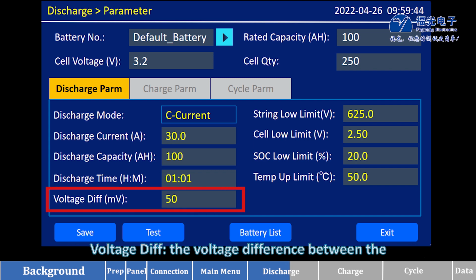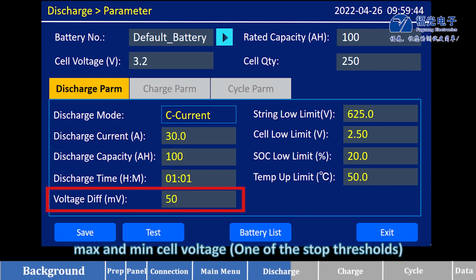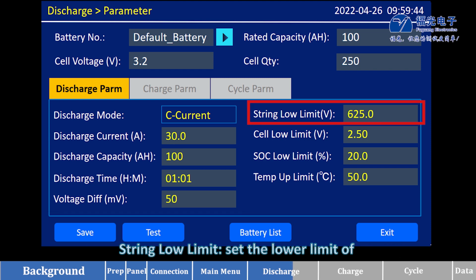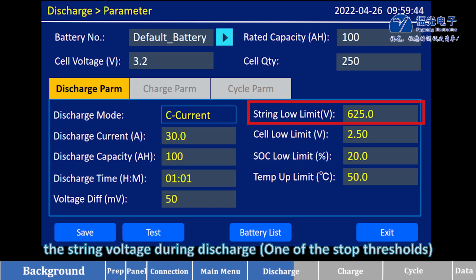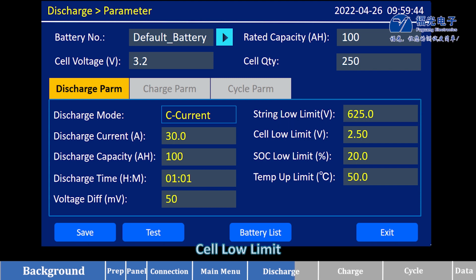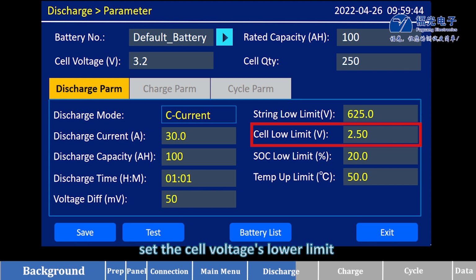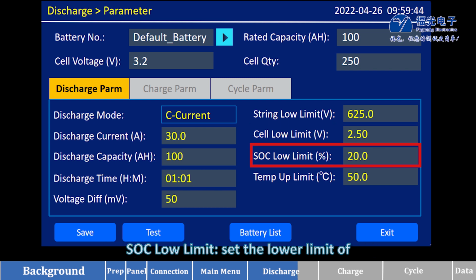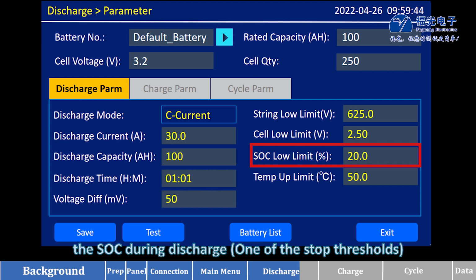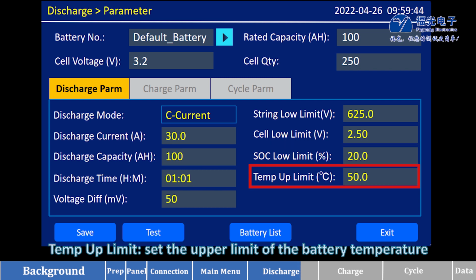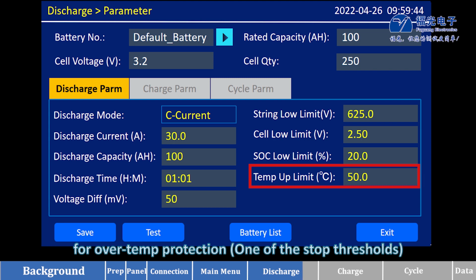Voltage difference. The voltage difference between the maximum and minimum cell voltage. String low limit. Set the lower limit of the string voltage during discharge. Cell low limit. Set the cell voltage's lower limit during discharge. SOC low limit. Set the lower limit of the state of charge during discharge. Temp up limit. Set the upper limit of the battery temperature for over temp protection.